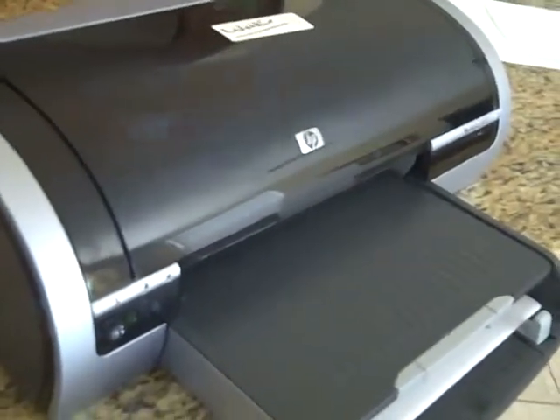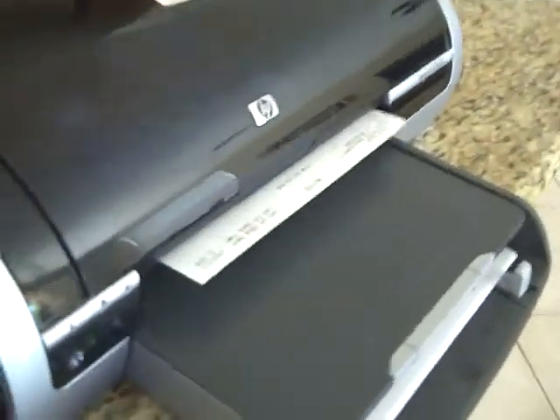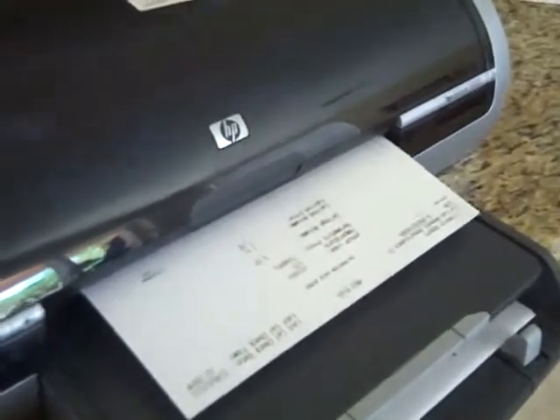And then it says calibration check, and it has the information there. So you want to hit print because we have to print and save, as I said, calibration done once at the beginning of each day. So you hit print, at which point the printer will print out the calibration check. And as I said, you only have to do this once at the beginning of each day. And it's only one page. And it has a graph at the bottom.